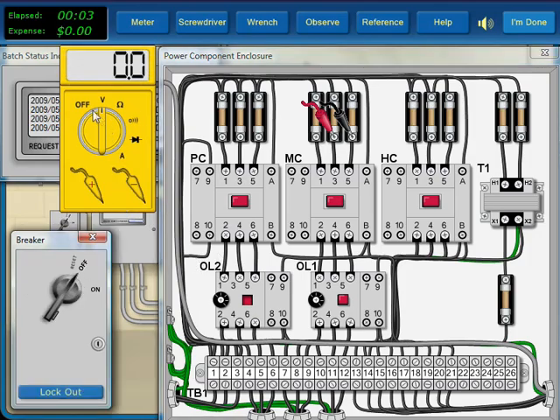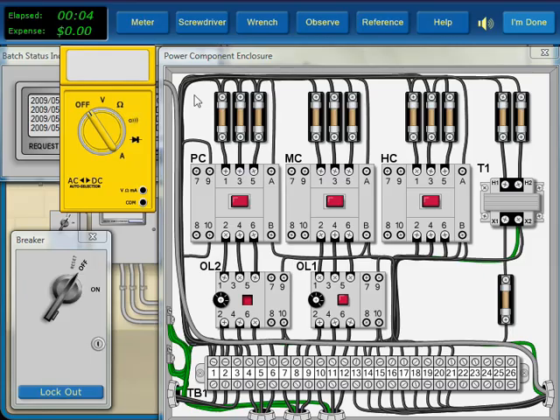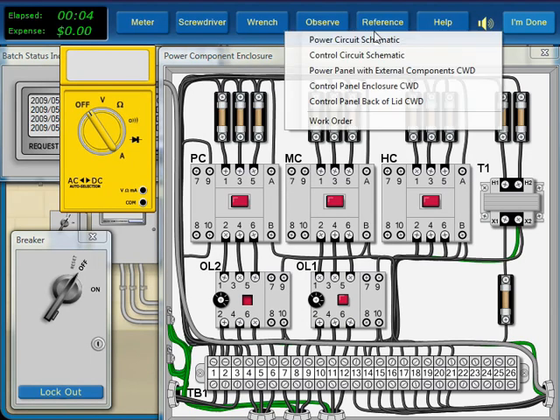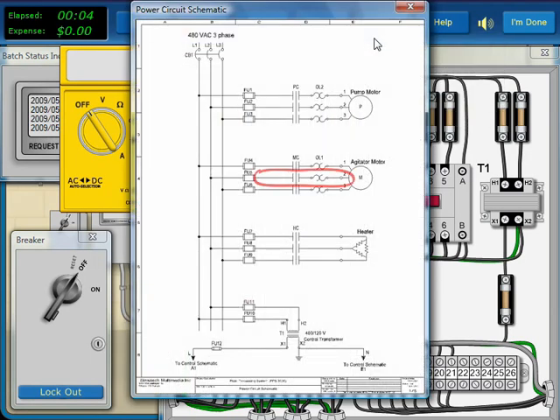We now know that the fault is an open in the center phase, somewhere between the bottom of the fuse and the motor star point. Since there is no obvious probable cause in the new problem area, we will need to perform tests to reduce it.